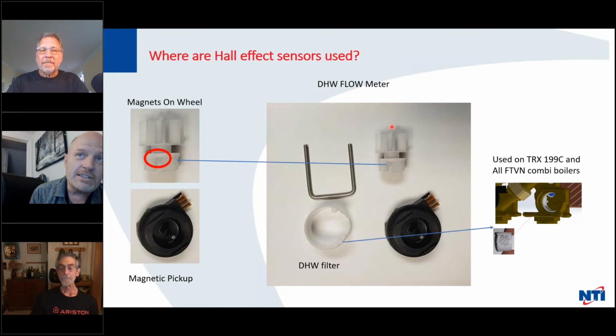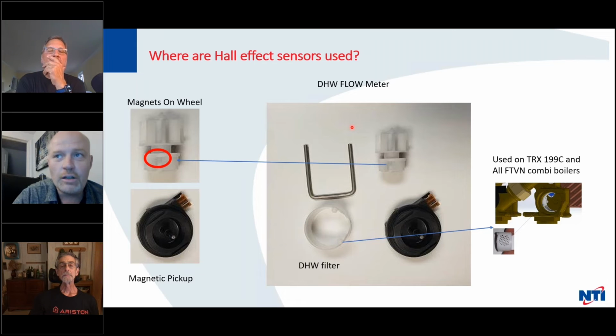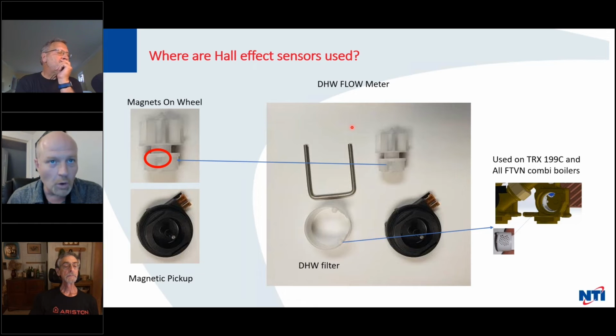The other thing we've seen is there's a little plastic point on the tip of this. Typically in cases where there's a recirculation line that's probably running 24/7, we see that this little pointed tip gets worn off and it becomes kind of flat and dull. And when that happens, there's too much friction inside the flow meter and it just doesn't spin very well.